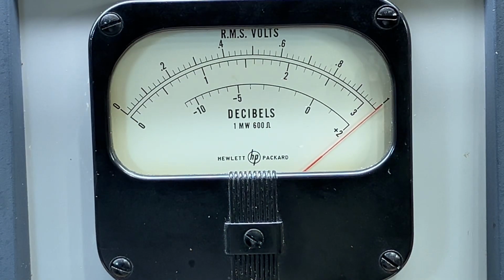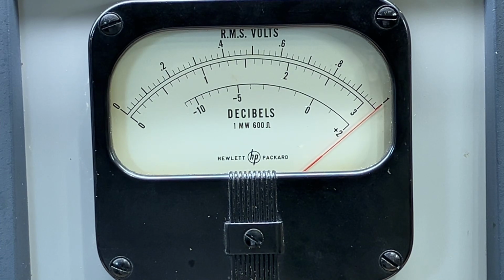Okay, so I've removed the meter and removed the front bezel from the meter and cleaned the glass on the back side of the glass. And there was also a little bit of some kind of something on the front of the glass. So I cleaned both sides of the glass and reassembled the meter, reinstalled it back in the instrument, realigned and calibrated the entire instrument. And now I want to just do a quick demonstration of the accuracy of this instrument.